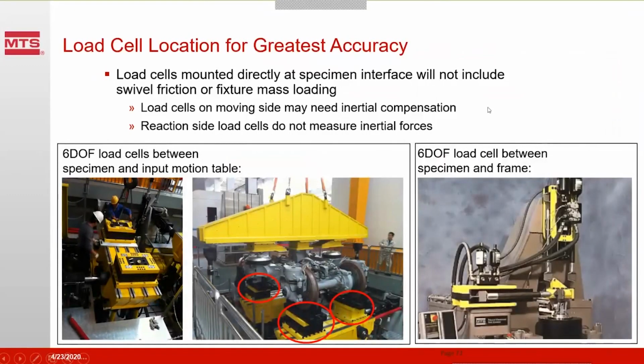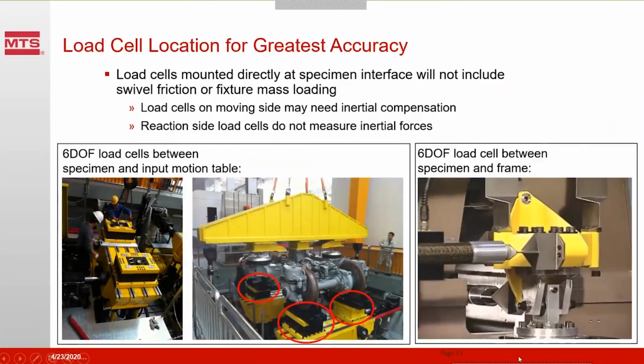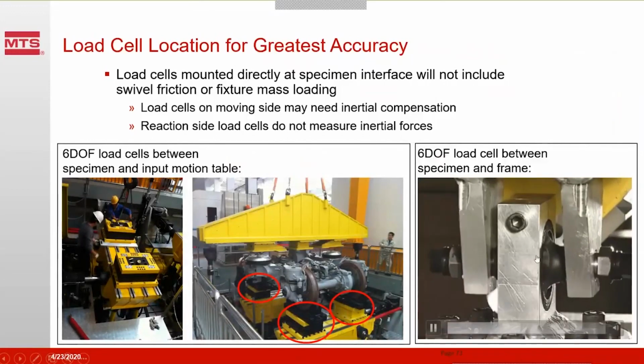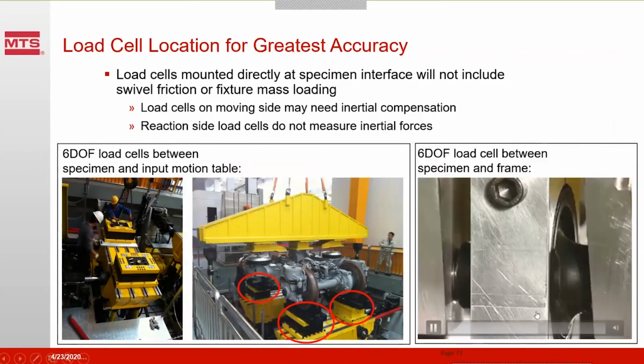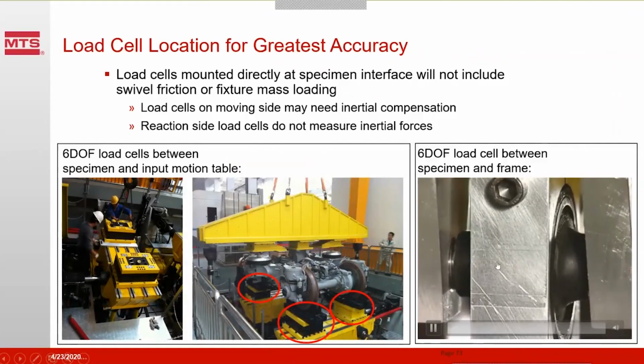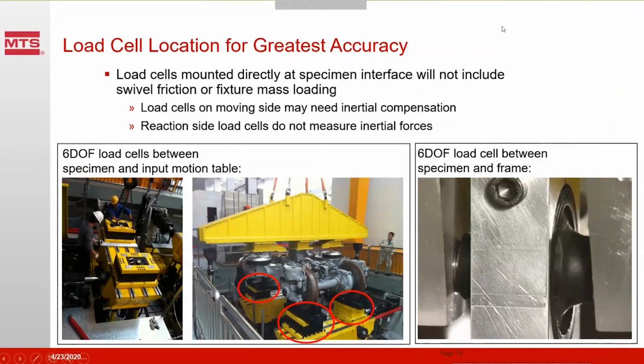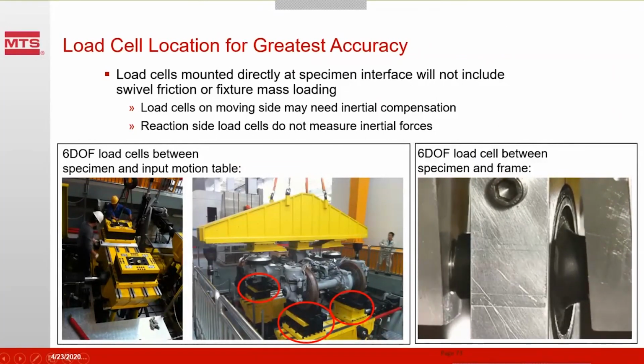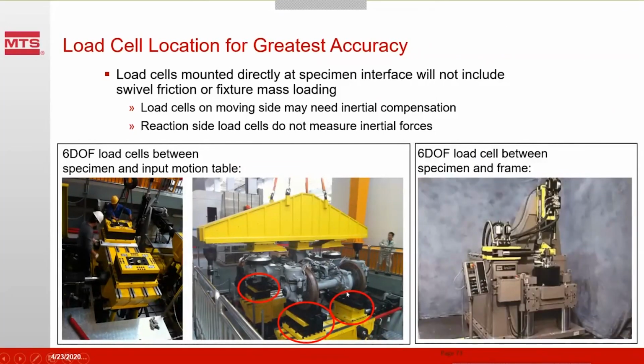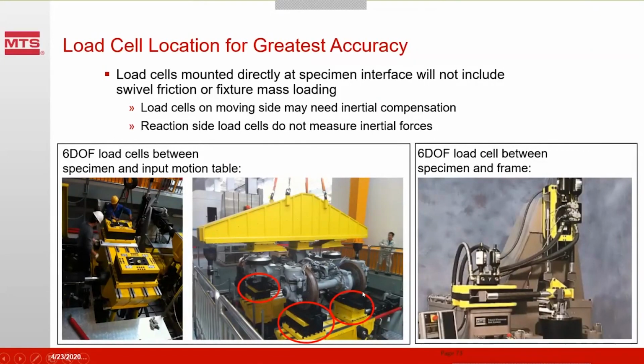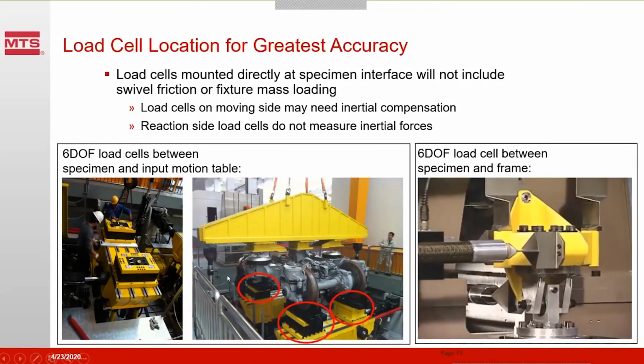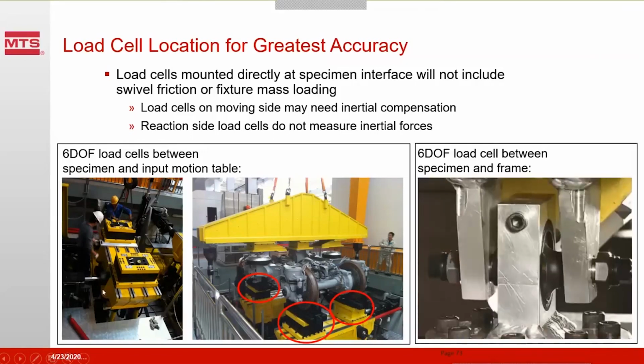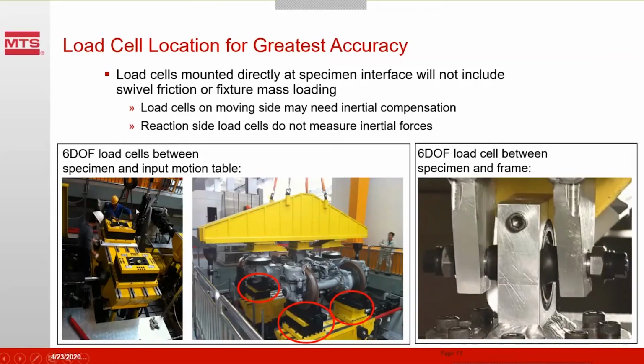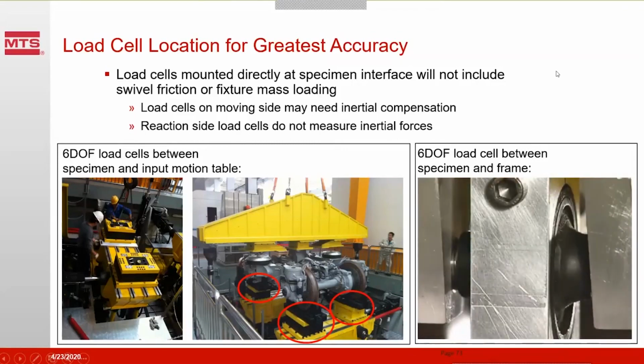Where's the best place for load transducers in terms of overall accuracy? Right at the point of input of the load or at the reaction point for the force? Very dynamic tests, we like it at the reaction side, such as you see here with this elastomer where there's a lot of motion going on. If we had the load cell on the moving side, we'd have to compensate for the inertial errors, the acceleration, and moving masses. If we put the load cell here, for example, to measure the forces into the train wheels, we need very little compensation. It's right where we need it. If we had transducers here on the actuators, the swivels would give a tremendous amount of error in the load outputs, and we wouldn't be able to measure the suspension characteristics very accurately.